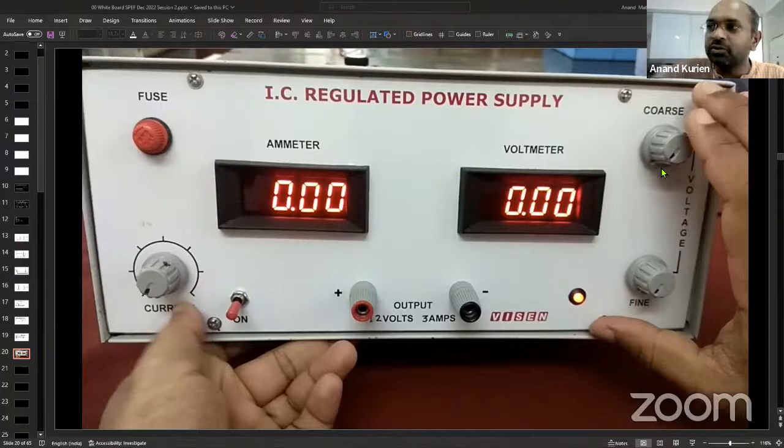So similarly, you put your ammeters, set it at 0.9, take one by one. That's why I said, if you have those banana cables, it's very simple. Take it, shove it in, write the value, pull it out, next, push it in. You can take 10, 20 voltmeters and it can be done in about 3 minutes. You can finish it. And if you write it all down, and all your voltmeters or ammeters are numbered, then you can see which numbered meter is misbehaving and take it out of your pile.